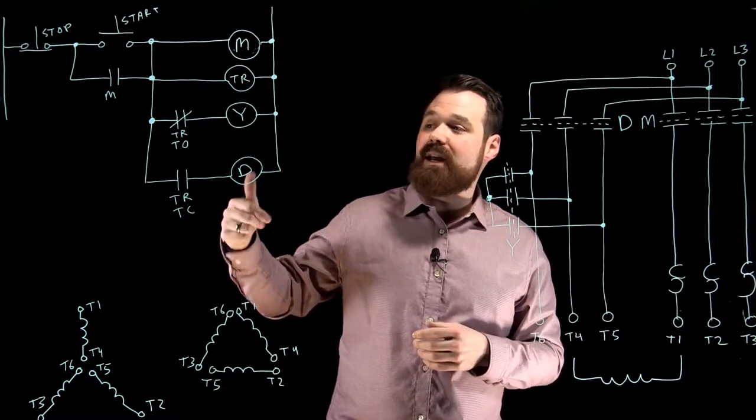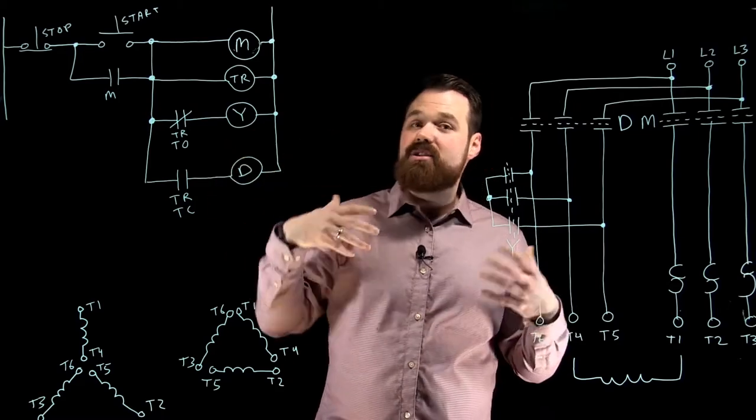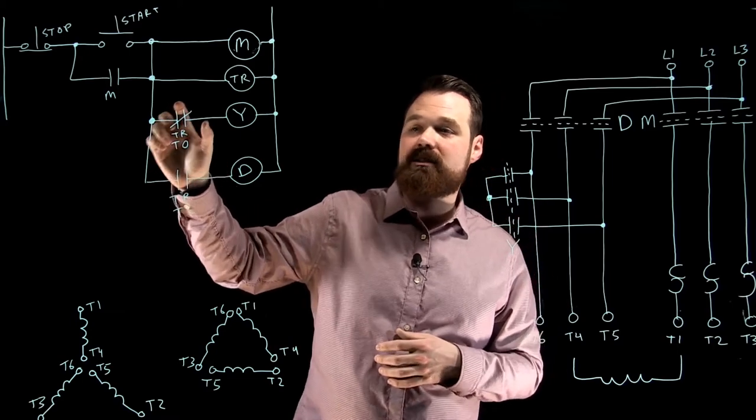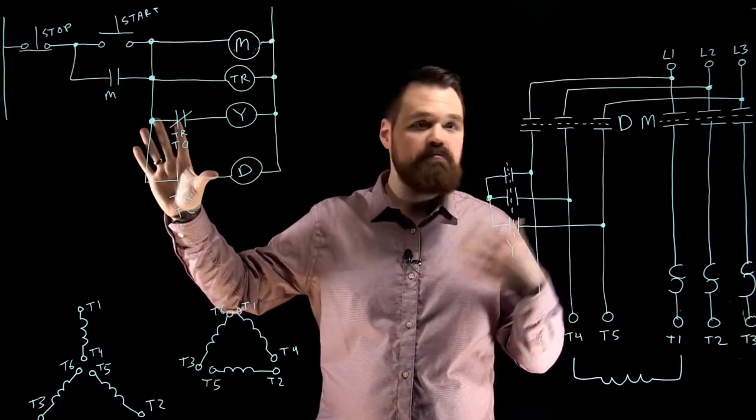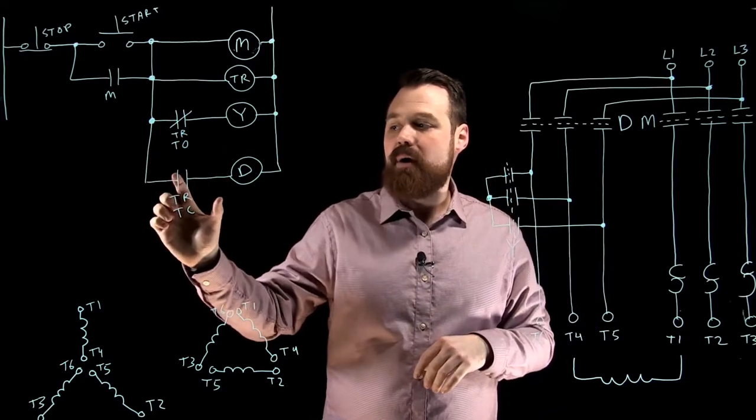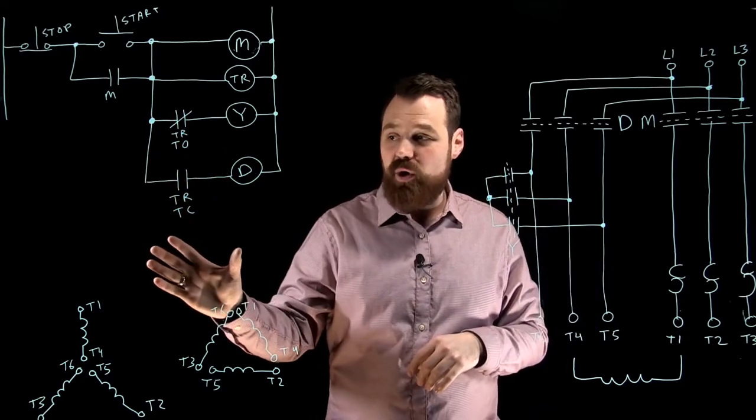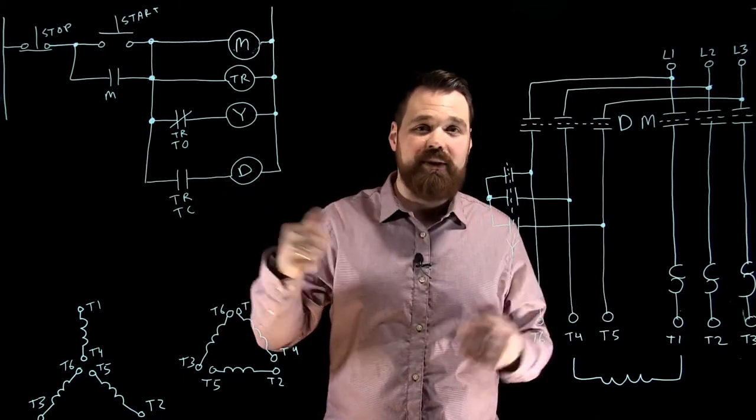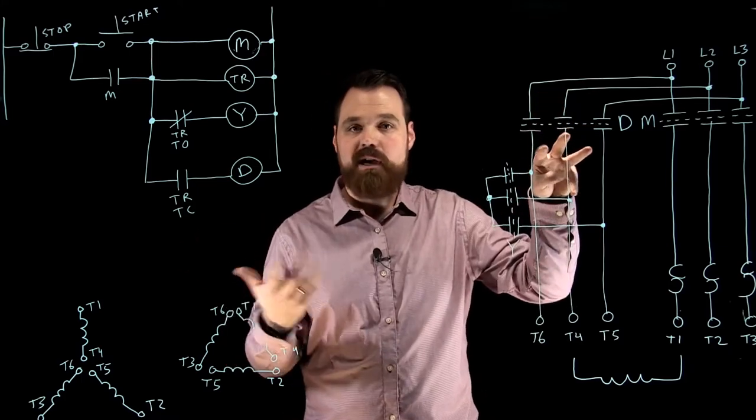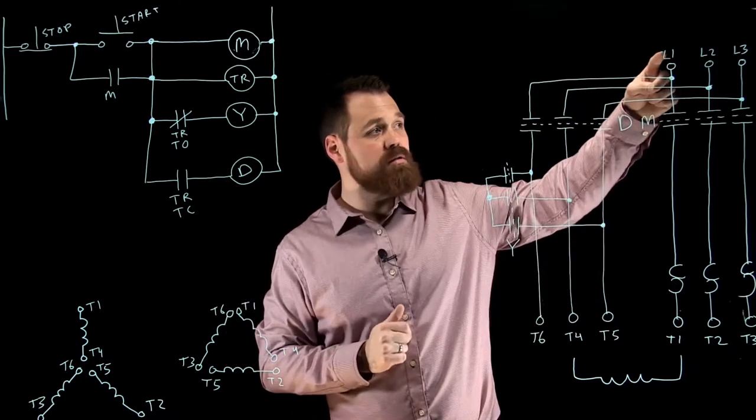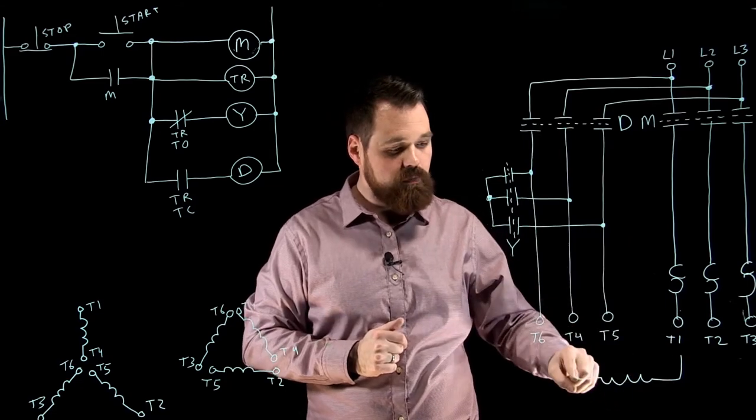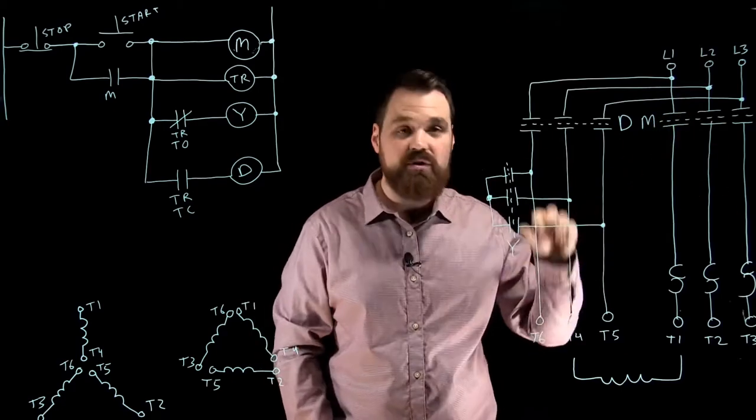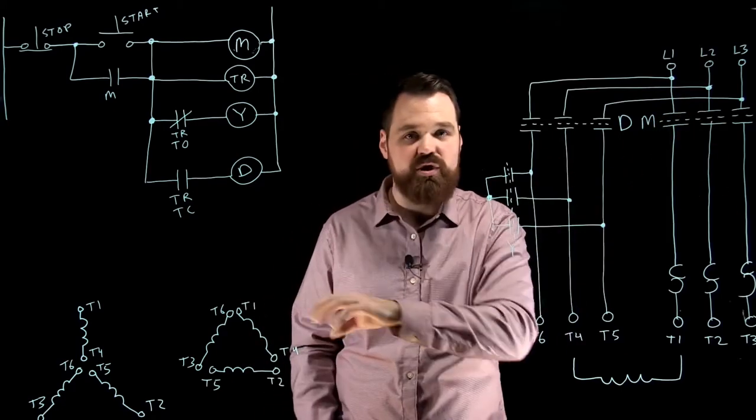Then what happens after a few seconds, this would be considered an open transition, because what would happen is my normally closed time to open contacts would open, basically de-energizing it in Y, and my normally open time to close contacts are going to close, energizing my D coil or my delta coil, which would close these sets of contacts. So now when current flows, it would flow through line 1 T4 and then back to the source, which would essentially put all of those into that delta formation, so we switched around that formation.